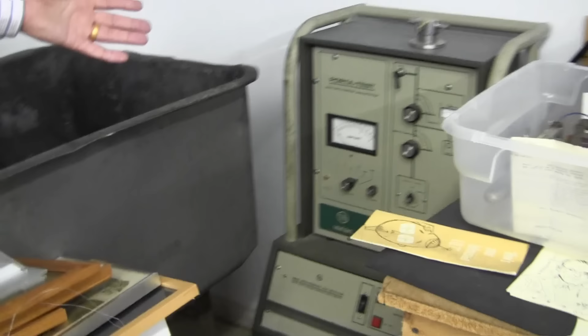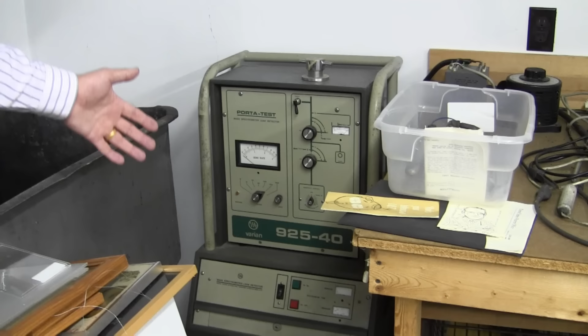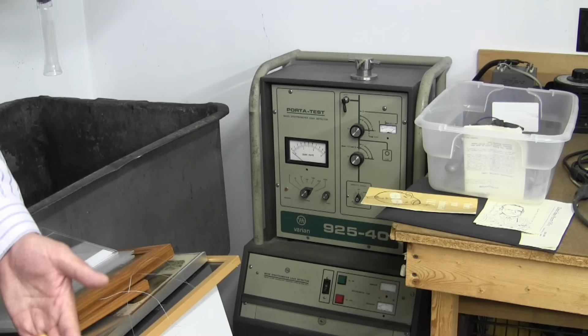And then the other thing I wanted to point out here, which is more of a piece of specialized equipment but is worth noting, is this specialized portable leak detector. The idea here is that we would apply helium to the outside of a piece of vacuum equipment while pumping the vacuum equipment down, meaning pulling the air out of it with the vacuum pump that's built into this, so that we can measure the leak rate of the tube. So not something that was normally done. This is a piece of laboratory equipment, but extremely useful if you're trying to troubleshoot your process and understand why you have a tube. This is a 15GP22, probably the most famous CRT in our community.